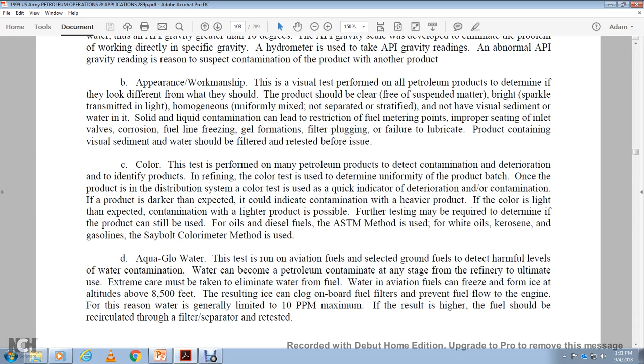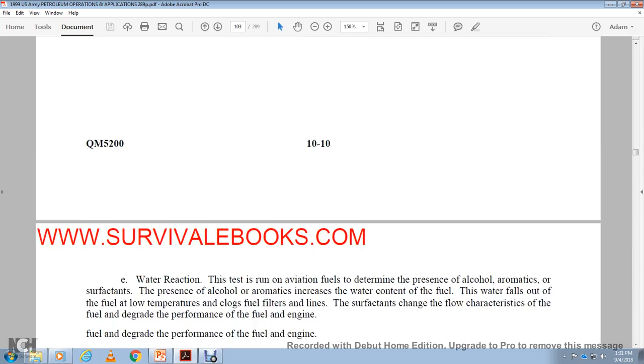Water in aviation fuels freezes into ice at altitudes of 8,500 feet. The resulting ice can clog onboard fuel filters, preventing fuel flow to the engine. Generally, the limit for water is 10 parts per million maximum. If the result is higher, the fuel should be recirculated, filtered, separated, and retested.